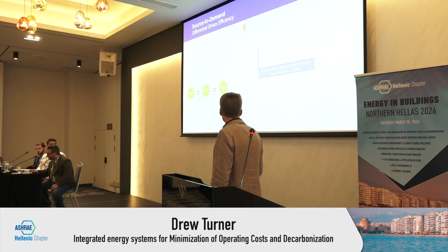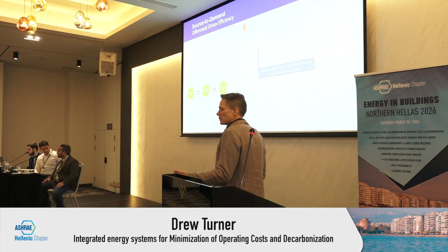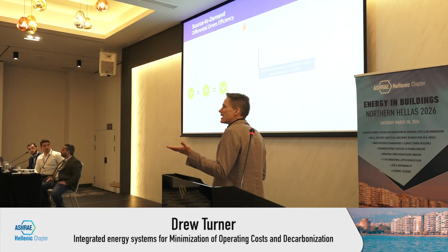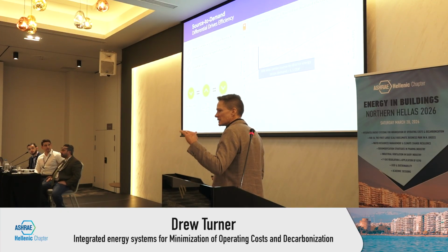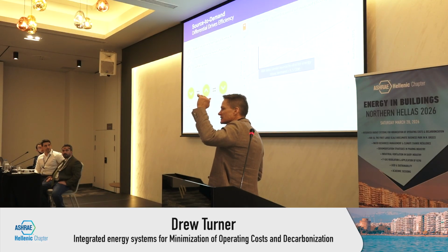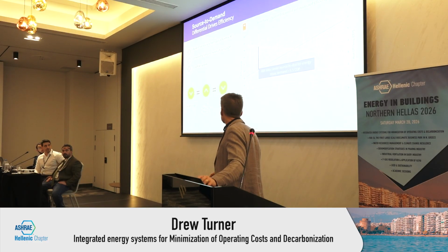So this is an example. If you have a 40K delta T from a data center with liquid cooling at about 35°C on the cooling side, that's what most are being designed for, and you're rejecting that to about 75°C for a district energy system, that's about 40K of work, which comes out to about a 5.5 COP.